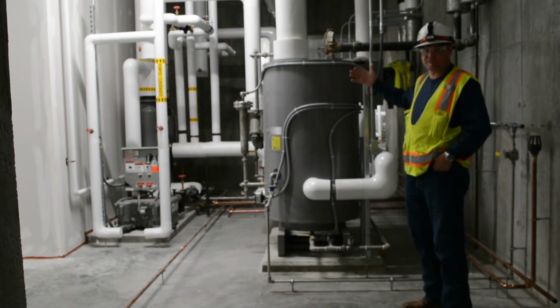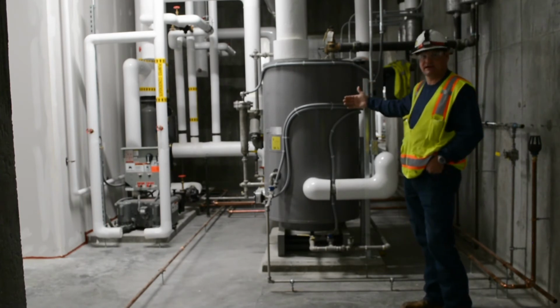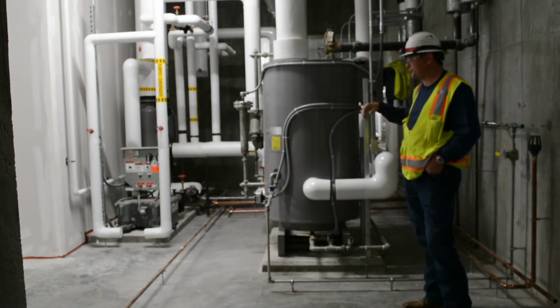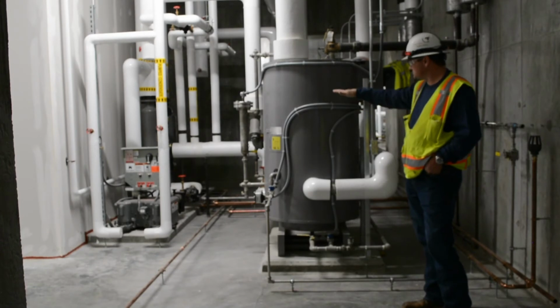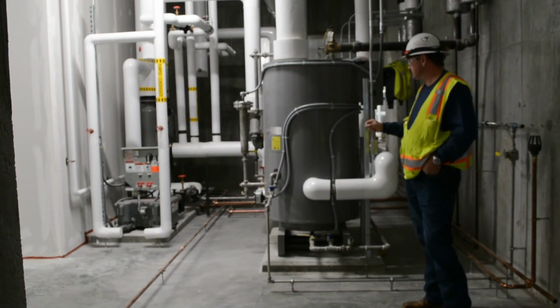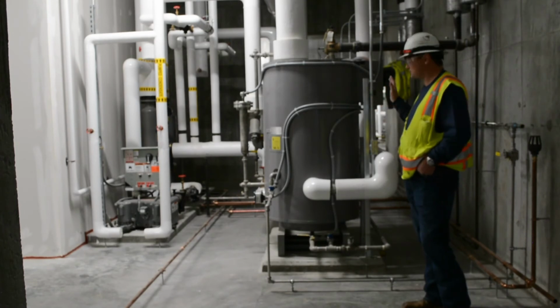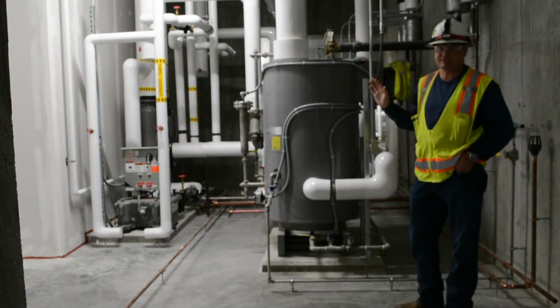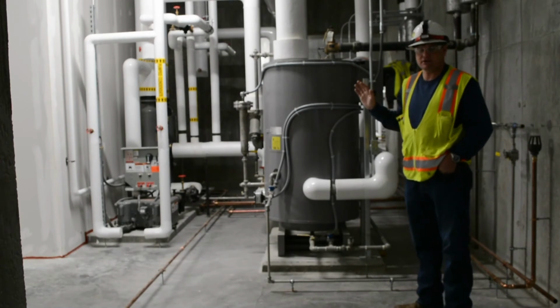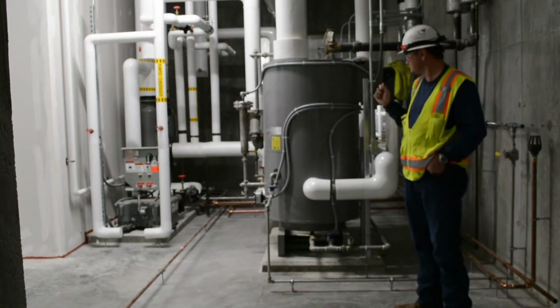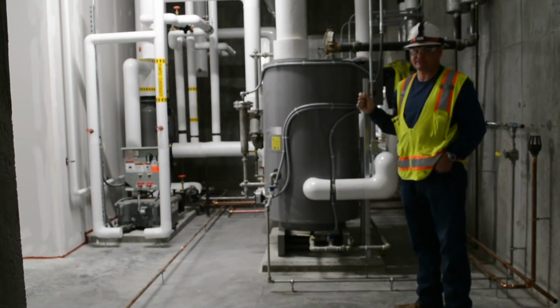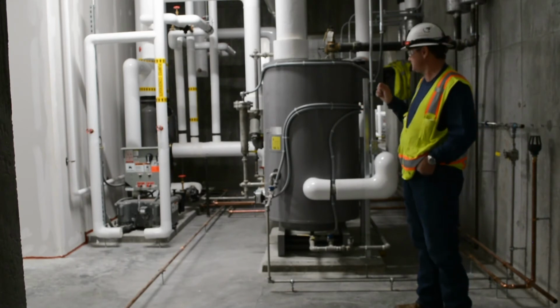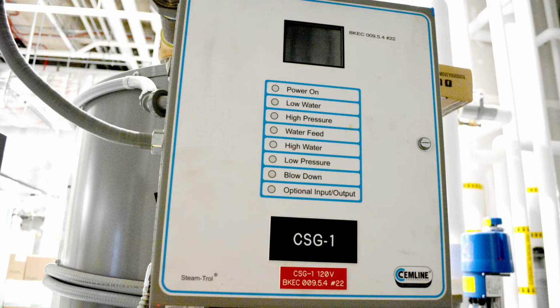It is a redundant set of boilers. You have one that can lead and take a majority of the load that's required, and in the event there's an issue with this one, it will automatically switch over to the other boiler. You'll need to obviously check the water level probes that are located on the back of the boiler. All of those set points are internal to the boiler. There's nothing that can be modified or changed through Metasys other than enable and disable. So you can basically turn it on and off, and that's about it. And then all the operational settings are contained within the main control board here.